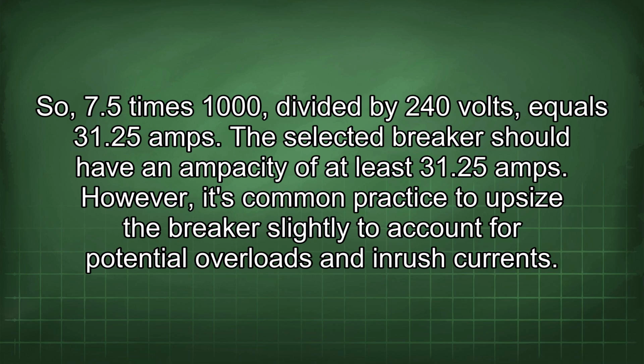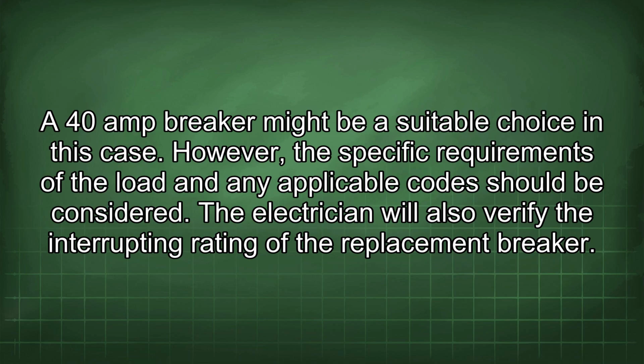However, it's common practice to upsize the breaker slightly to account for potential overloads and inrush currents. A 40 amp breaker might be a suitable choice in this case. However, the specific requirements of the load and any applicable codes should be considered. The electrician will also verify the interrupting rating of the replacement breaker.